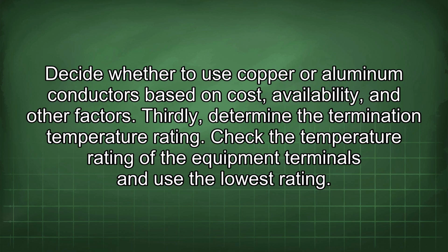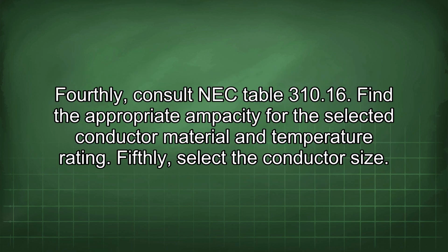Decide whether to use copper or aluminum conductors based on cost, availability, and other factors. Thirdly, determine the termination temperature rating. Check the temperature rating of the equipment terminals and use the lowest rating. Fourthly, consult NEC Table 310.16. Find the appropriate ampacity for the selected conductor material and temperature rating.